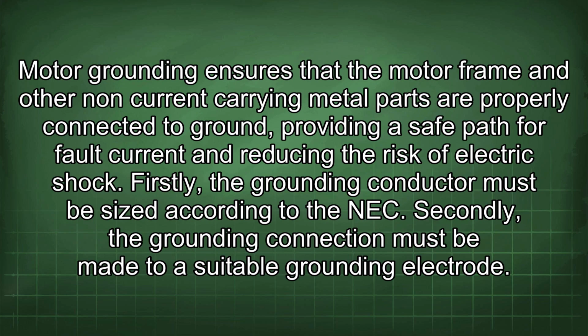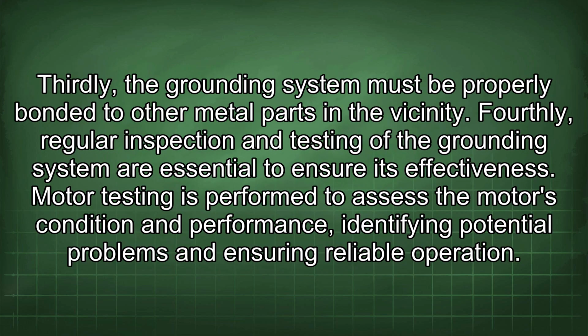Motor grounding ensures that the motor frame and other non-current carrying metal parts are properly connected to ground, providing a safe path for fault current and reducing the risk of electric shock. Firstly, the grounding conductor must be sized according to the NEC. Secondly, the grounding connection must be made to a suitable grounding electrode. Thirdly, the grounding system must be properly bonded to other metal parts in the vicinity. Fourthly, regular inspection and testing of the grounding system are essential to ensure its effectiveness.